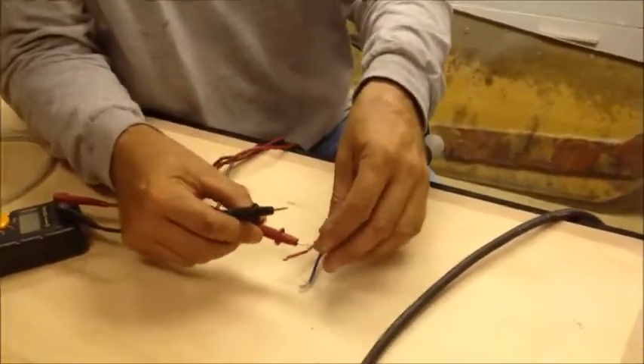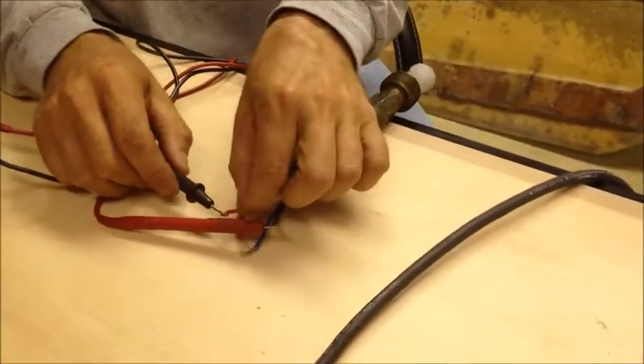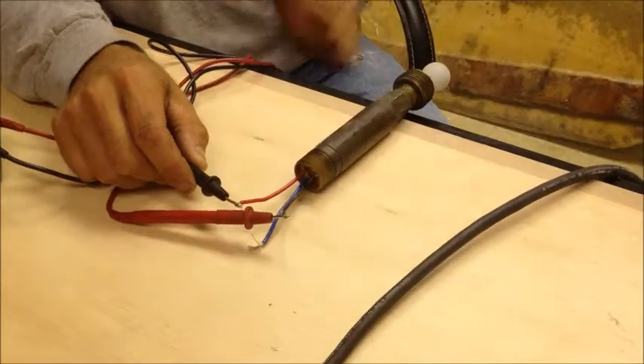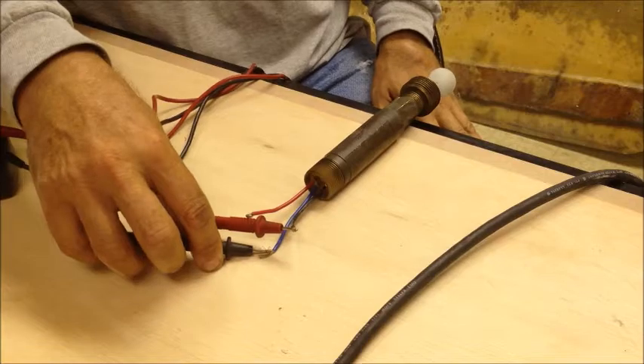Usually the blacks are the common, so we would hook one end of our probe to a black wire and we check. So this must be the normal open wire and this blue wire is the normally closed.